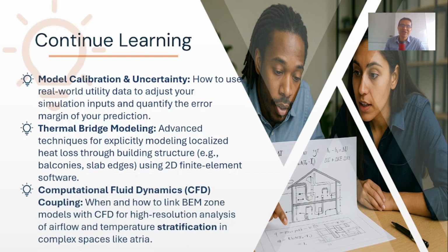Finally, explore computational fluid dynamics, coupling the BEM with these models. We discussed that a thermal zone assumes perfectly mixed air, but that's not true in complex spaces like large atriums or theaters. CFD coupling allows you to link your zone model with a detailed fluid dynamic simulation, giving you a high-resolution view of air movement and temperature stratification.